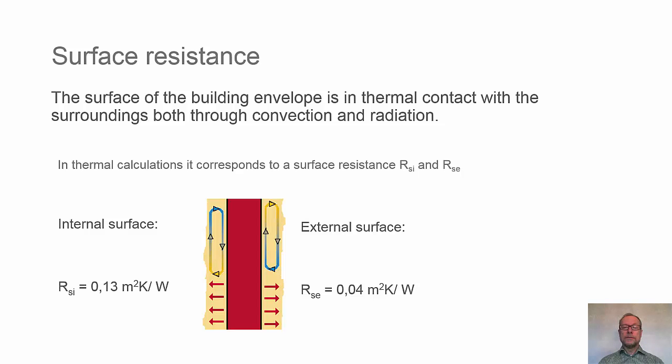And on the inside we call it RSI, surface interior, and an external one RSE. These are default values: 0.13 square meter Kelvin per Watt on the inside, and 0.04 square meter Kelvin per Watt on the outside. The surface resistance is lower on the outside since we have more air movements due to wind, so the convective part of the surface resistance is lower.